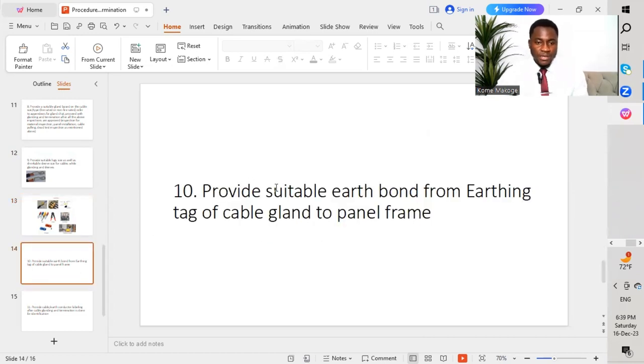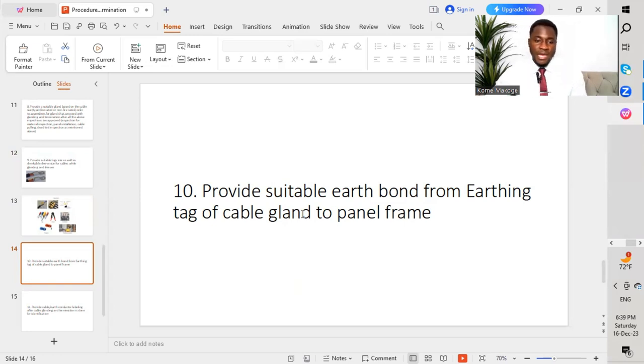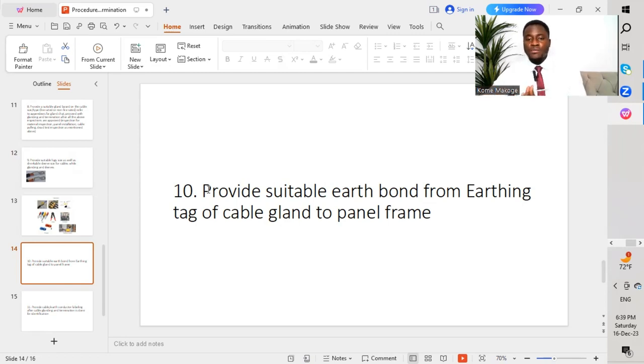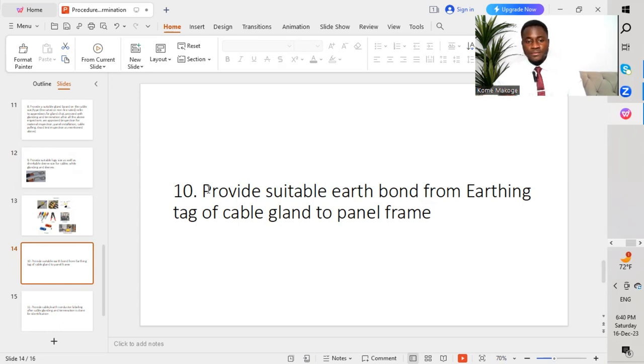The tenth point: provide a suitable earth bond from the cable gland earth tag to the panel frame. This is very important — after carrying out glanding and termination, we provide a suitable bonding conductor from the cable earth tag and connect it to the panel frame to ensure earth continuity.